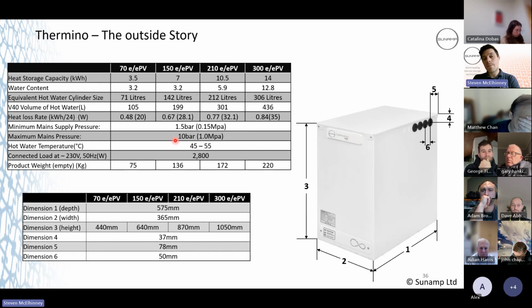So say you've had a failure of the pressure reducing valve, and you've got a 10 bar expansion relief valve on the pipework somewhere. The heat exchanger will be able to take it. But if you keep supplying that heat battery with 10 bar of pressure, it's obviously not going to be that great for it. So what we ask is for people to limit it to 5, and you should be plain sailing from there.